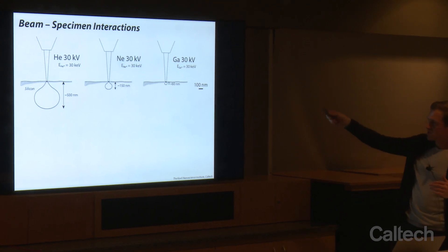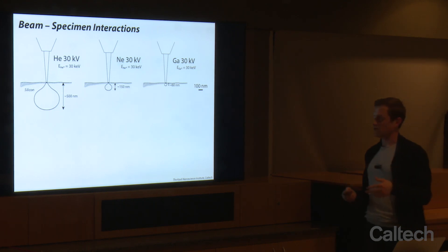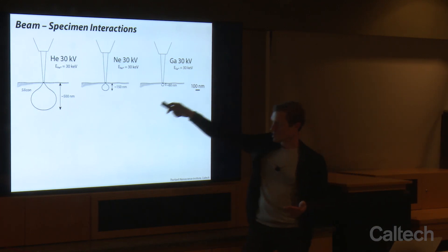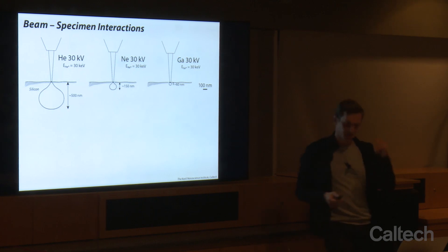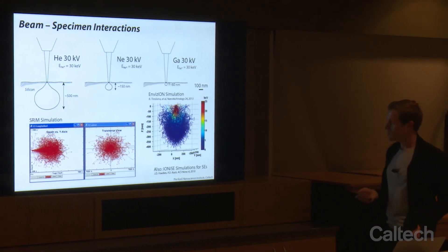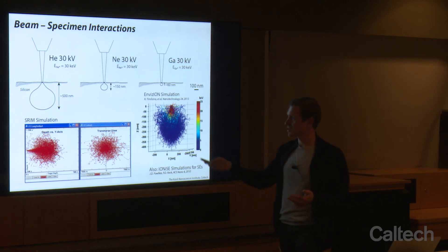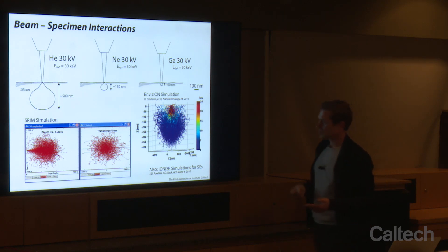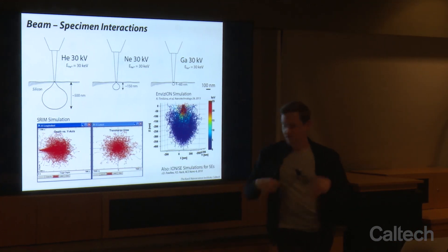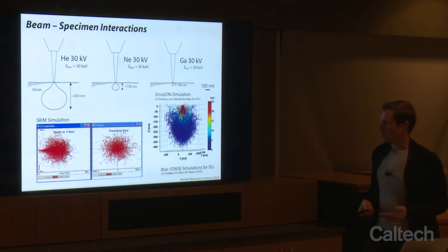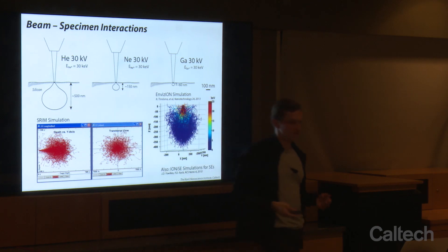We can look at different ion species — helium, neon, and gallium. For each one at 30 kV, each ion has 30 keV in energy. For helium, the stopping power isn't as great, so we might get 500 nanometers penetration in silicon; 150 nanometers for 30 kV neon; and 60 nanometers for gallium. We can simulate these using SRIM — Stopping and Range of Ions in Matter — the most common simulation used in the field. You pick your ion species, energy, and show what the scattering looks like in the specimen. It doesn't simulate an evolving surface or sputtering, so you can't simulate making a via, but it shows your damage zone as a function of energy and ion species. Other simulation software includes EnvizION and IONiSE, which are being developed more in academia.